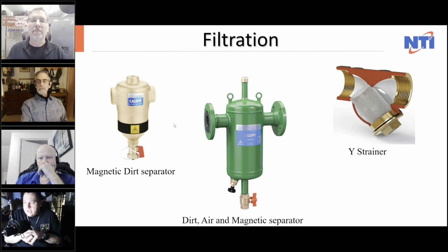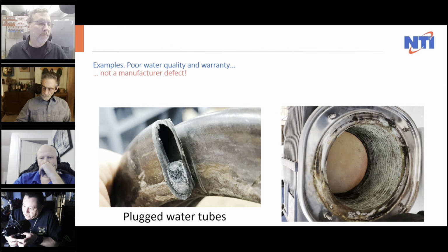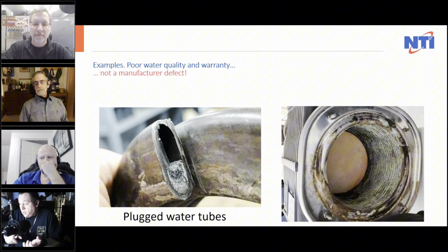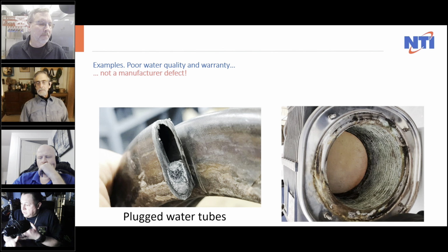So what does the magnetite do? As I explained earlier, the magnetite sits down inside the bottom of the heat exchanger as water moves through and creates flow. It hardens because it's cooking that sediment, causing it to get as hard as cement. At that point we're restricting flow in the heat exchanger and causing stress, because the burner is heating up trying to heat that vessel while magnetite sits in the bottom. This causes future problems, leaks, and will also cause lockouts because the exhaust gases can't get out from the bottom of the heat exchanger. So a lot of stuff goes on there.